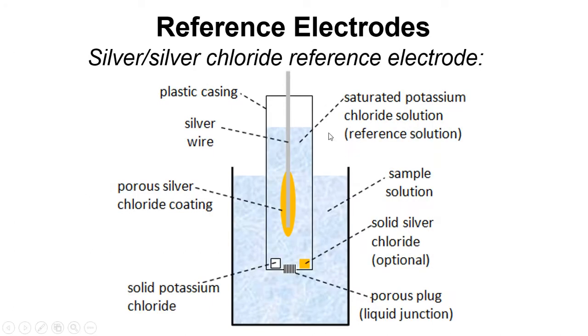For the reference electrode, we have the silver wire with the silver chloride coating, a reference solution of saturated potassium chloride, and the liquid junction is formed by the diffusion of KCl across the junction, which minimizes the liquid junction potential. Within the saturated potassium chloride solution, we first add some solid silver chloride so that the solution becomes saturated in silver chloride — this prevents the coating from dissolving. We also add some solid potassium chloride so that if KCl diffuses out, the concentration can be maintained at saturation.